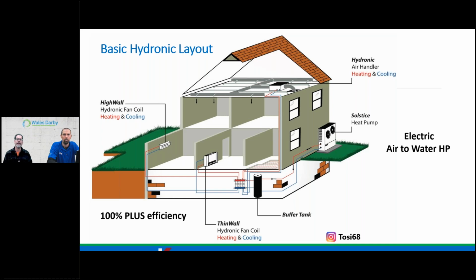We were talking about the buffer tank here. And if you see, this is just a snapshot of what modern-day heating could be for someone's home, right? So we have a lot of different emitters. We can use air, we can use a hydro coil as long as it's sized for a lower water temperature. Certainly have radiant involved here, and we have some really cool cabinets or even wall mounted, what looks like a mini split. That's not refrigerant, that's water. So these are factors of, wow, I didn't know we have the ability to take an emitter that I would think I would need baseboard, and now I can mount this thing high on the wall, like maybe a kitchen.